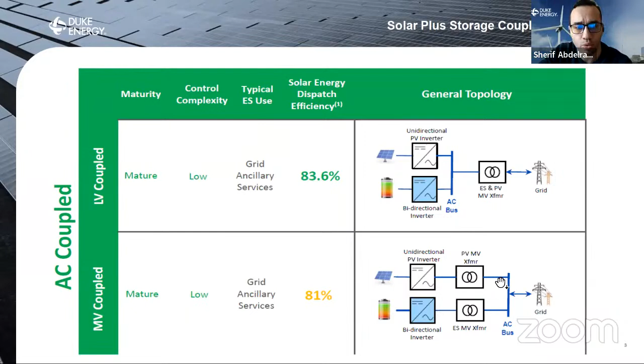They enable you to perform grid ancillary services, since you have a dedicated inverter for your battery system, almost totally decoupled from your solar resource, especially if your interconnection allows both to operate at the same time. On efficiency, low voltage coupled systems get a bit higher efficiency than medium voltage coupled systems, because you avoid the additional step of going through the medium voltage PV transformer to the medium voltage energy storage transformer and then discharging back to the grid. So that's where you get a bit higher efficiency for solar energy dispatch to the grid.